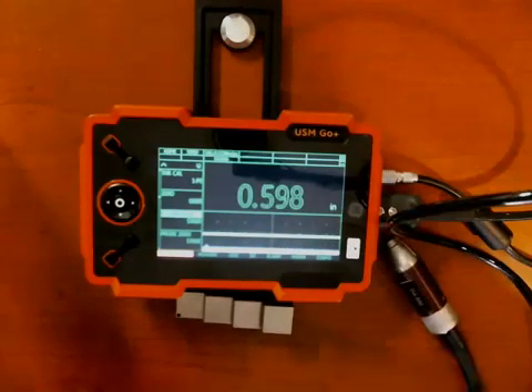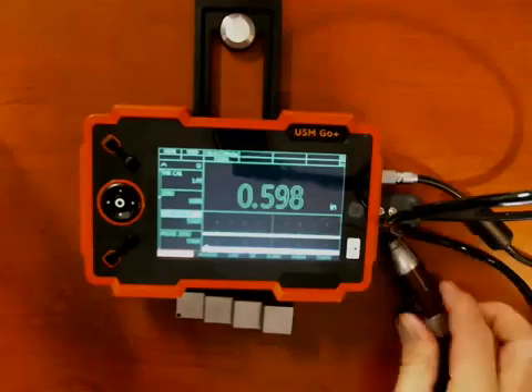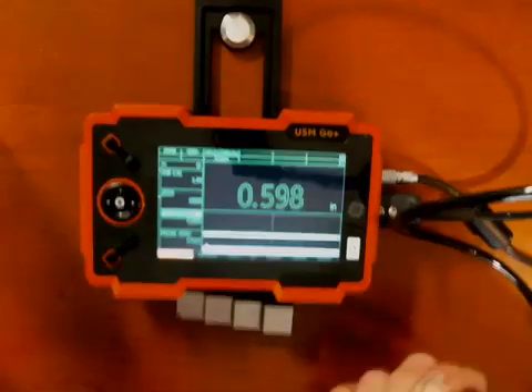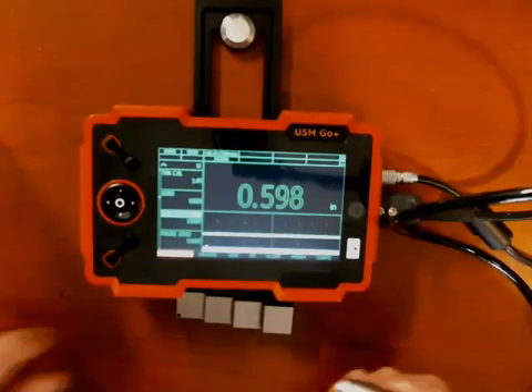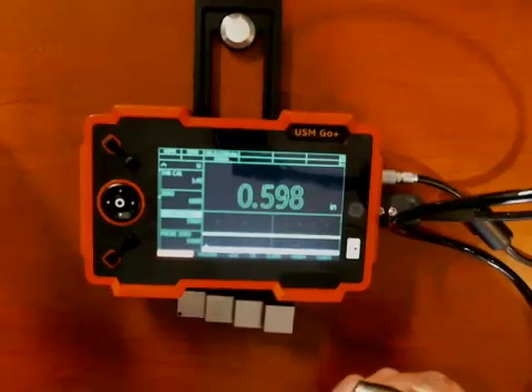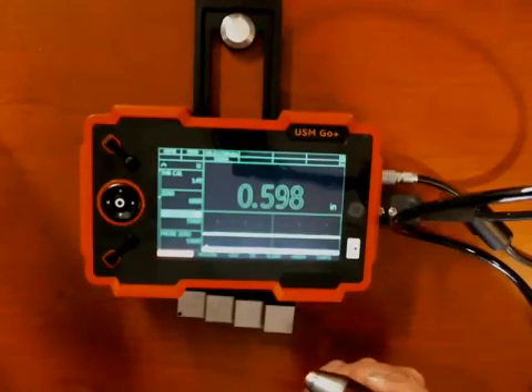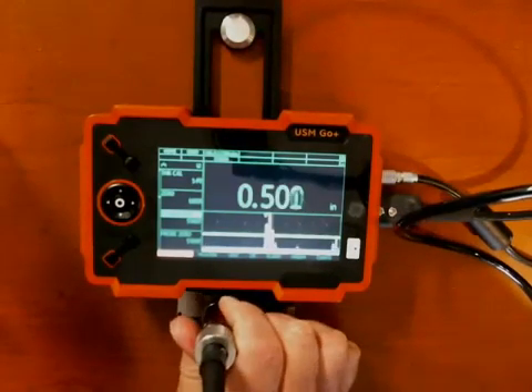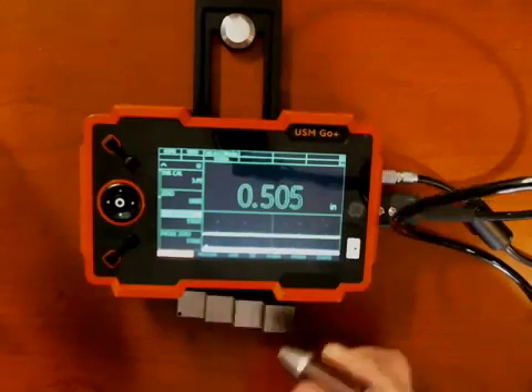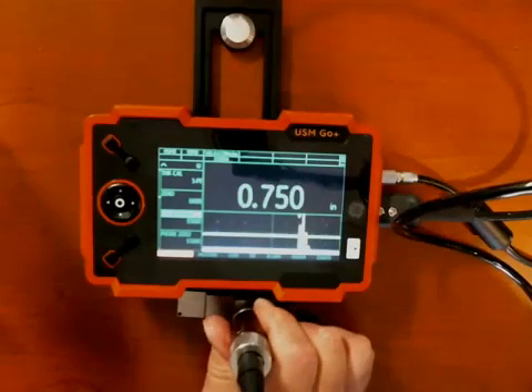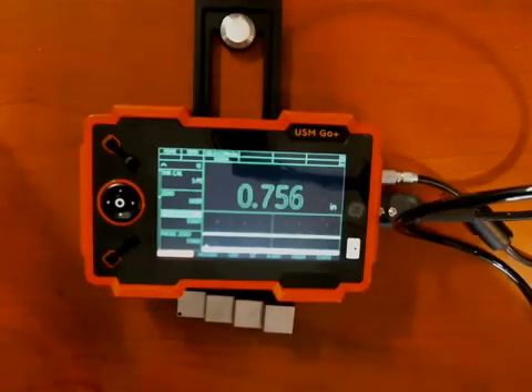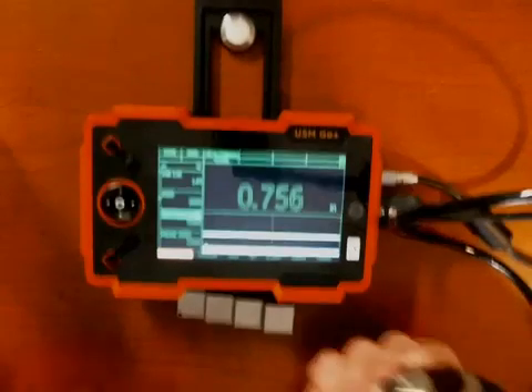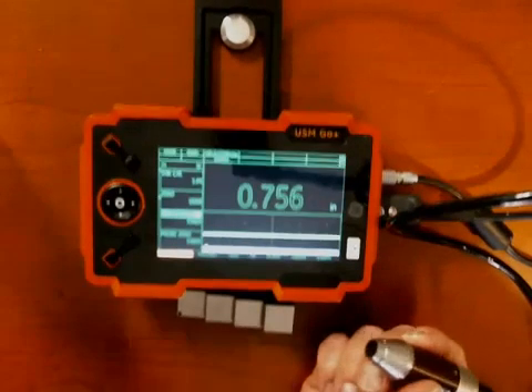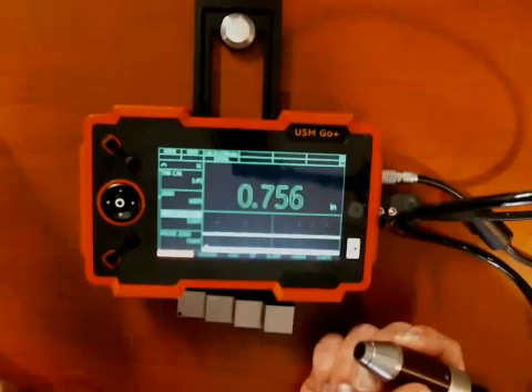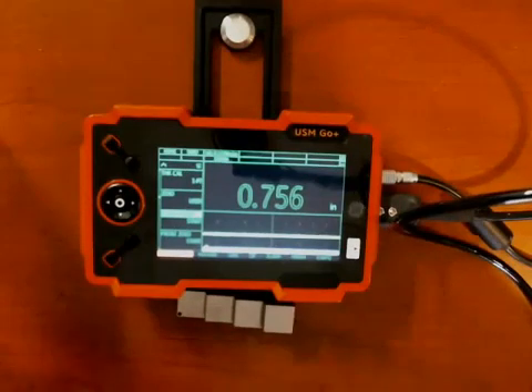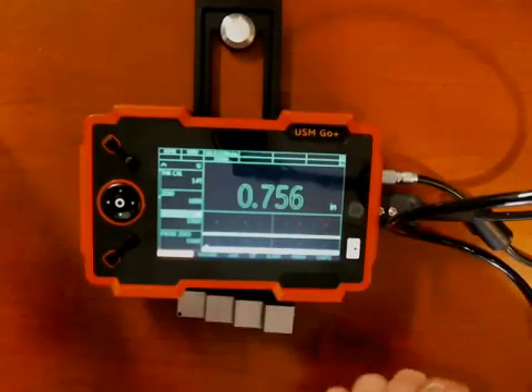And at this point, I'm all set to go inspect carbon steel plate and pipe and things like that and take good accurate measurements. I would normally keep my block with me, a couple of times a day I come back and check a step on the block, just make sure that I'm still getting accurate readings. If things would start to drift, as the probe starts to wear, you might go back through the calibration process again to make sure that the 0 is correct.